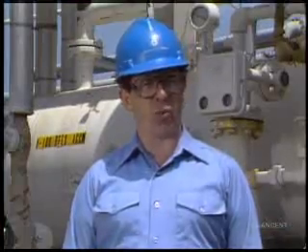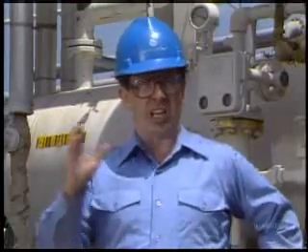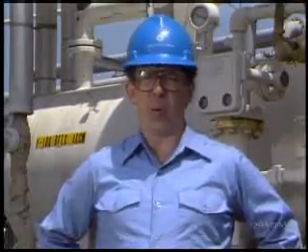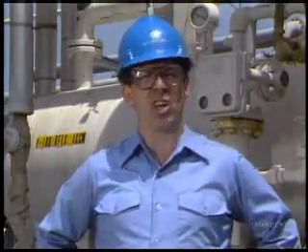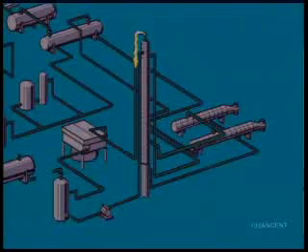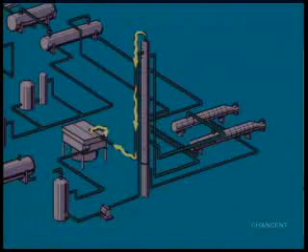Reflux is a process where a fluid is removed from a vessel, condensed, and returned to the vessel to enhance the process. The reflux system consists of the reflux condenser, accumulator, and pump. Overhead vapors from the stripper, mainly consisting of water vapor and acid gases, pass through the reflux condenser, which condenses most of the water vapor and the small amount of amine solution which may have vaporized in the stripper.